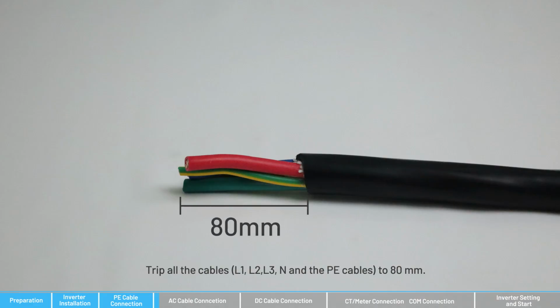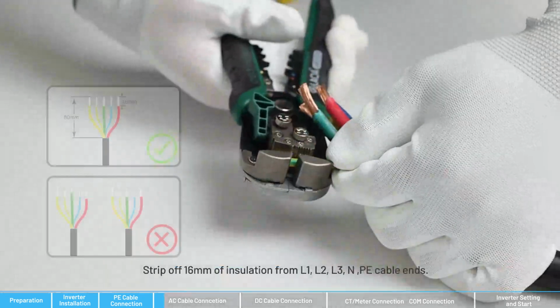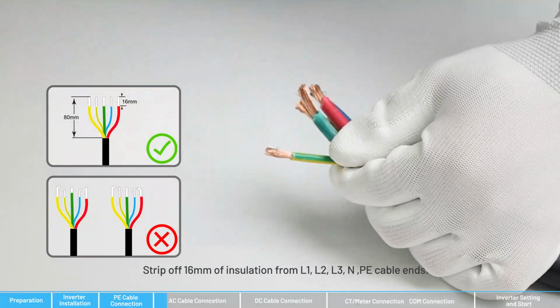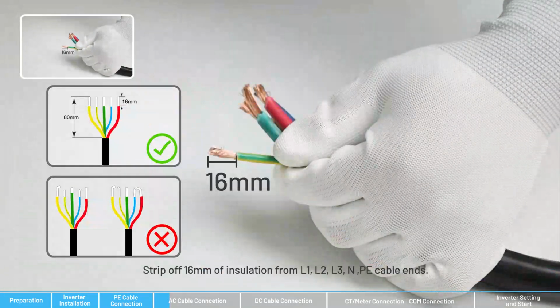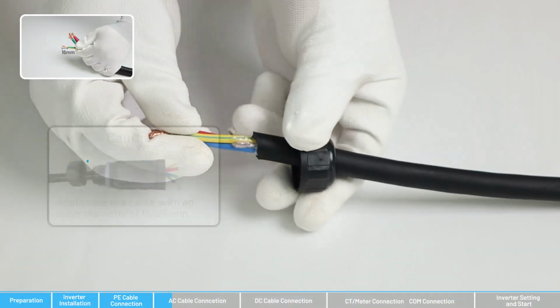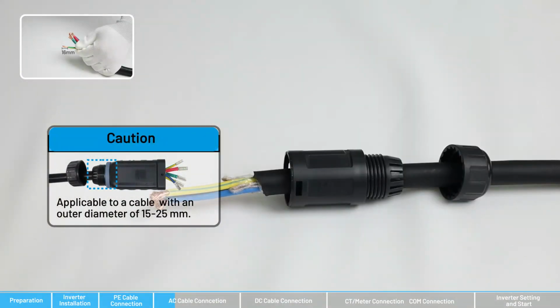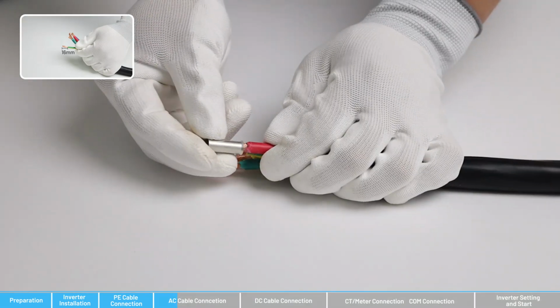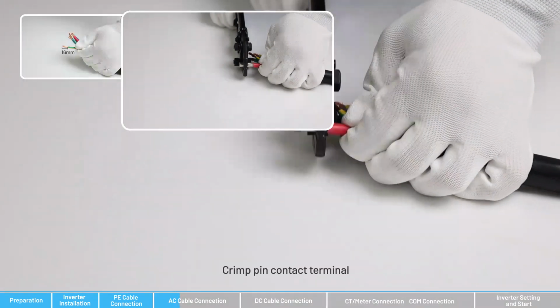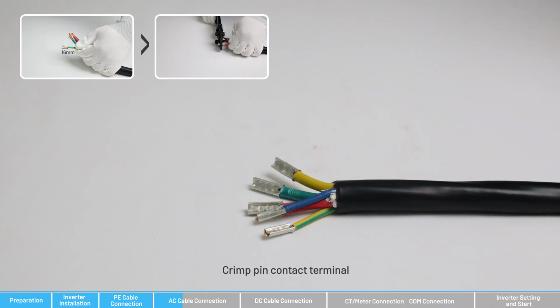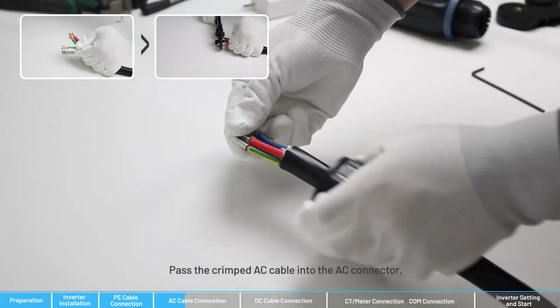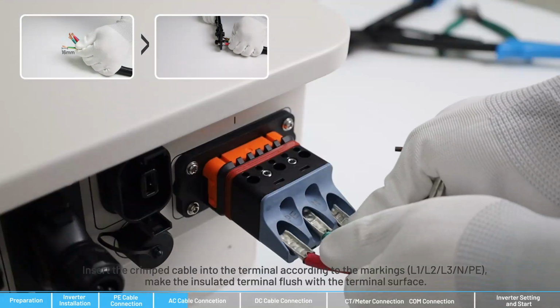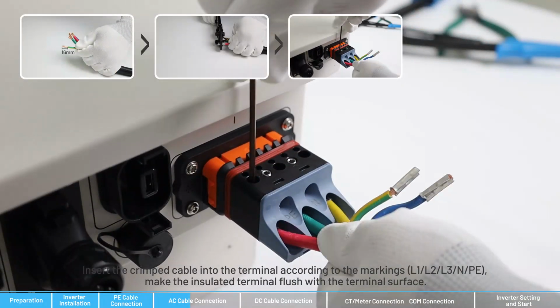Trim all the cables, L1, L2, L3, N, and the PE cable, to 80 mm. Strip off 16 mm of insulation from the L1, L2, L3, N, PE cable ends. Crimp the pin contact terminal. Pass the crimped AC cable into the AC connector.